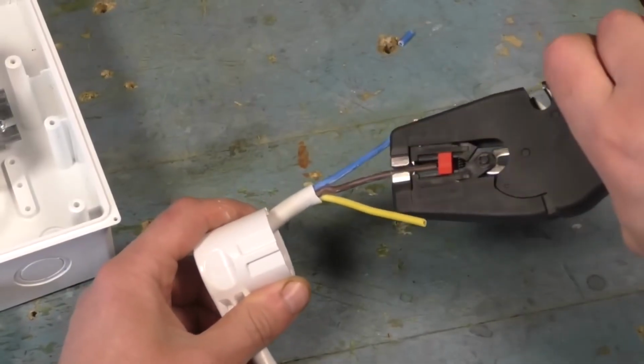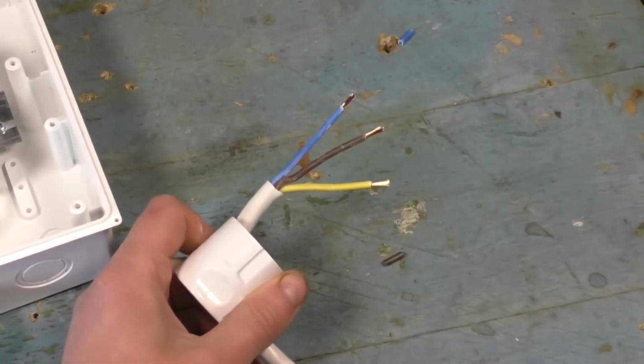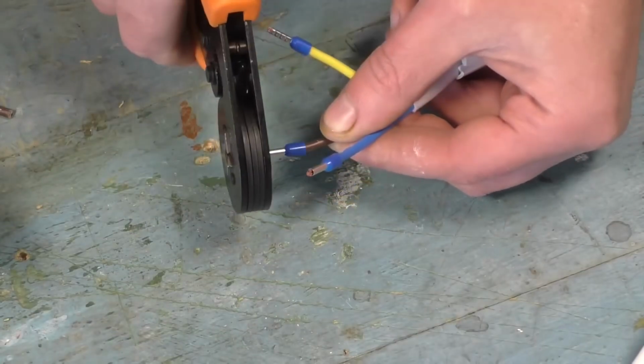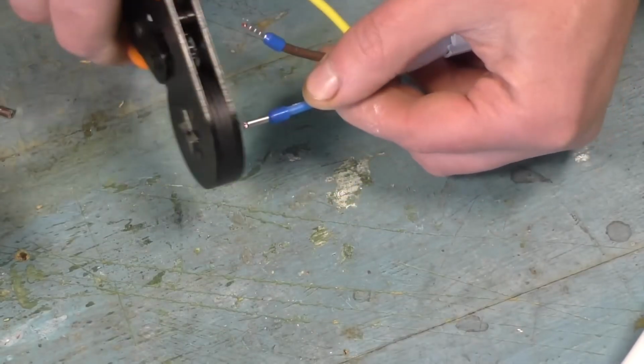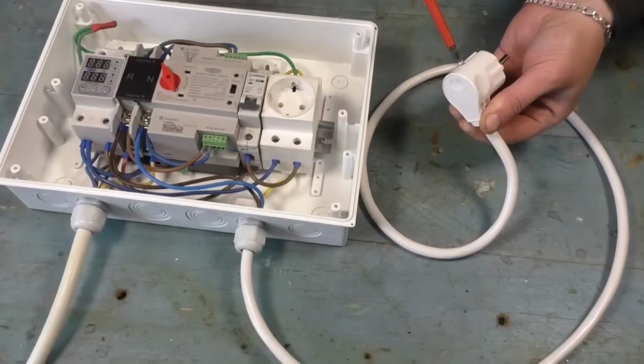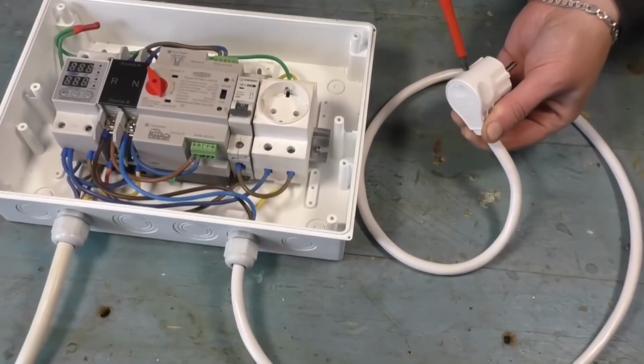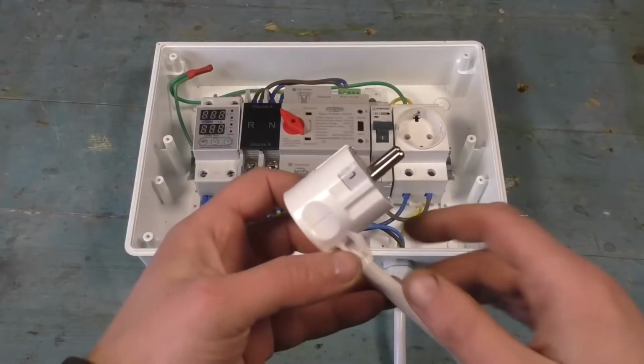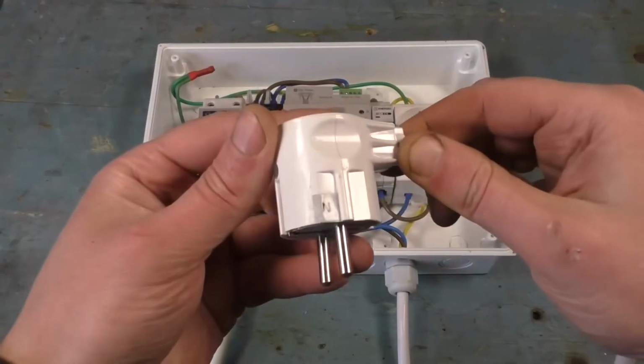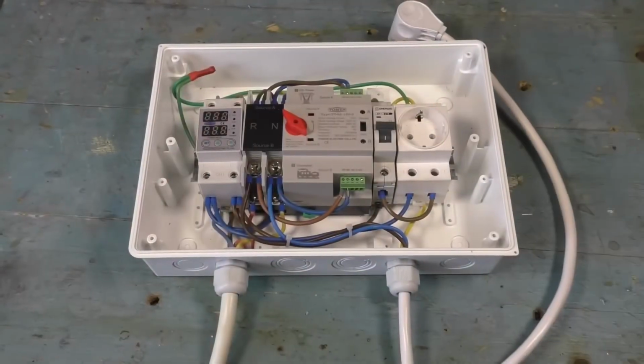Remove the insulation and then crimp each conductor. The plug should be of good quality since it will be connected to the output of the charging station. I connected the plug contacts according to the charging station socket standard, neutral on the left, phase on the right. Additionally, I labeled everything so nothing gets mixed up.